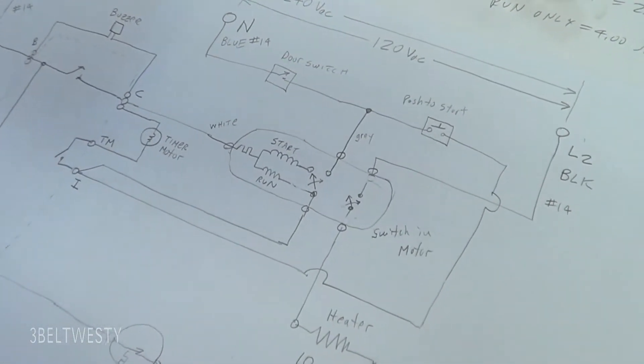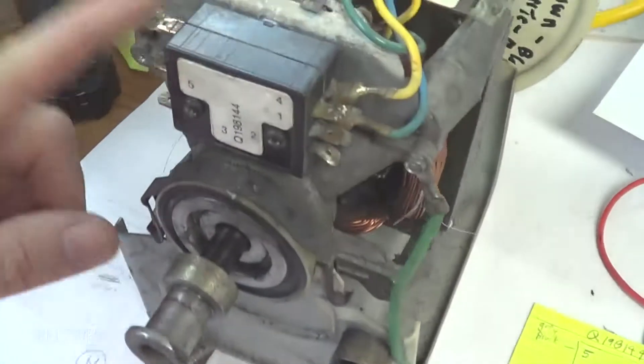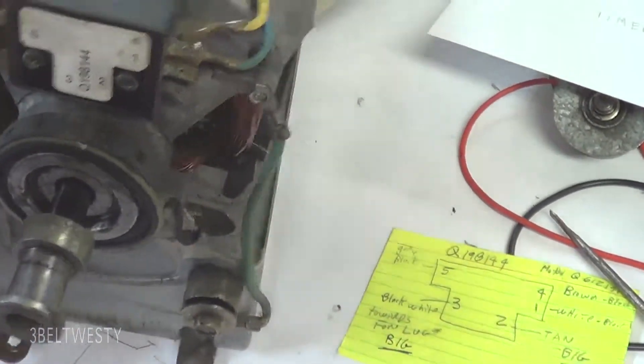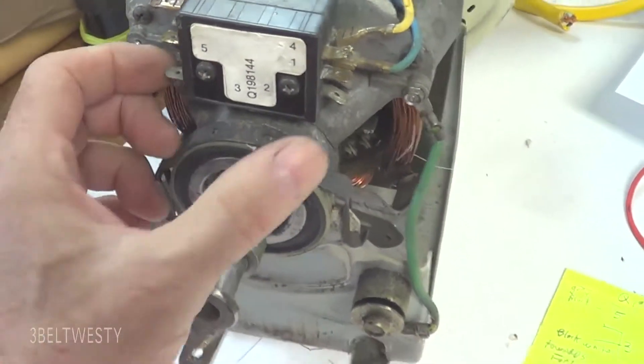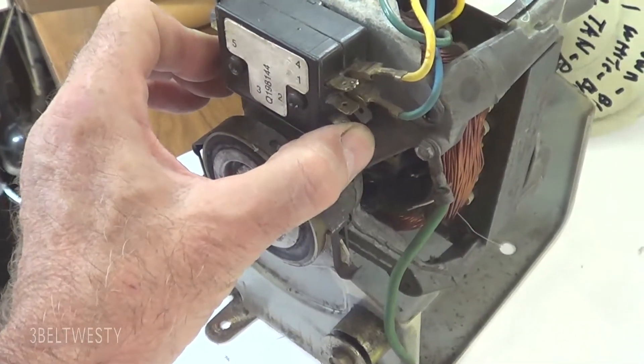So, I didn't see anything obvious, but I went ahead and pulled the motor out. This is a centrifugal clutch here that is used to turn off the windings. These two lugs down here have the big wires that connect up so that the motor has to turn before the heater comes on.